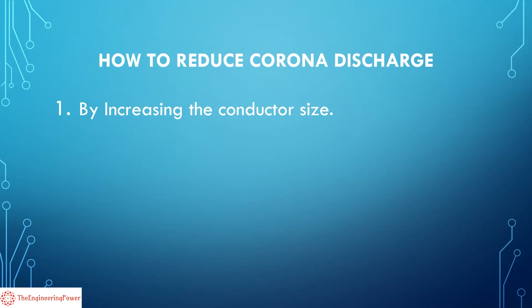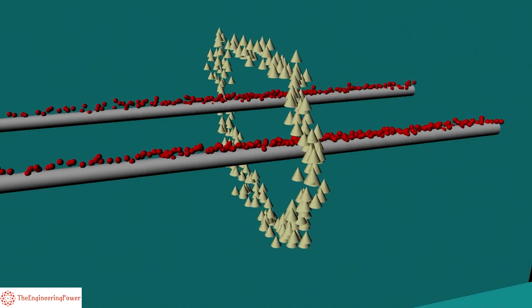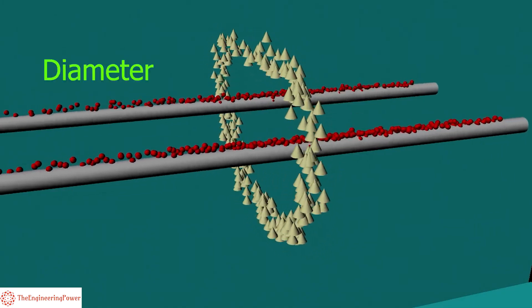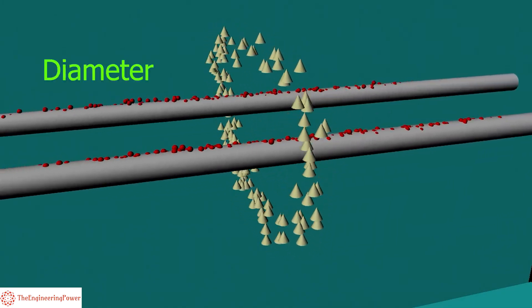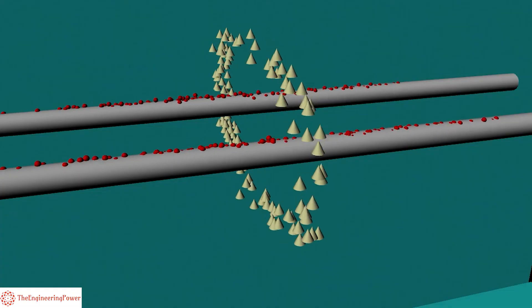Now we discuss some of the methods to reduce corona discharge. The first method is by increasing the conductor size. By increasing the diameter of the conductor, the corona discharge can be reduced. That is why ACSR conductors are mostly used on high voltage transmission lines because of their larger cross-sectional areas.